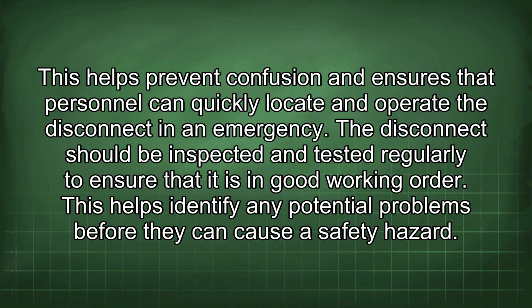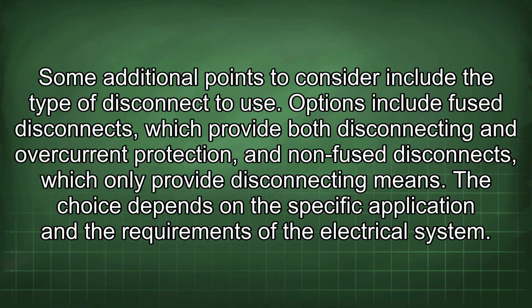The disconnect should be inspected and tested regularly to ensure that it is in good working order. This helps identify any potential problems before they can cause a safety hazard. Some additional points to consider include the type of disconnect to use. Options include fused disconnects, which provide both disconnecting and overcurrent protection, and non-fused disconnects, which only provide disconnecting means. The choice depends on the specific application and the requirements of the electrical system.